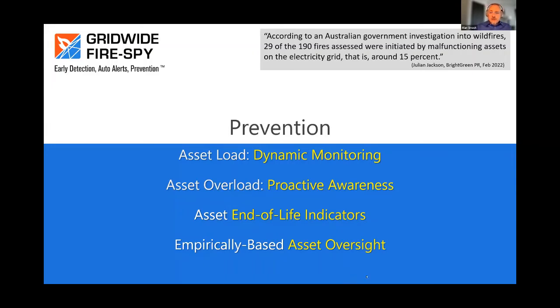That's really where we're trying to go with this technology through Grid-Wide Fire Spy. I've listed asset load monitoring as very important, since we're now seeing substantial overload conditions developing in grids, much of it driven by EV charging stations—an unplanned load that wasn't imagined one, two, or three decades ago when many transformers were deployed. These grid edge impacts weren't anticipated, and EV charging stations create one of those substantial unplanned impacts.